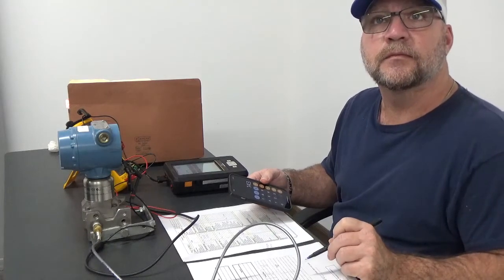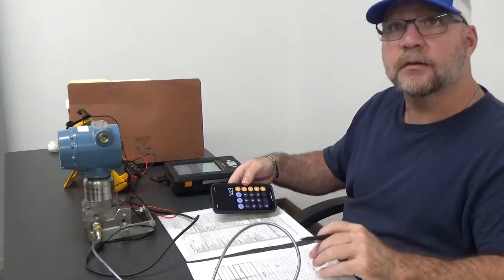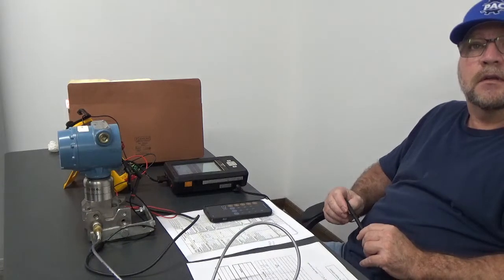Okay, so what I want you to do is, before you calibrate, you calculate. You remember that formula that we gave you? Yes, sir. I got it in mind. If you remember it and you got a way to do it, that's fine. But I want you to check it before you calibrate it. I want you to do an as found.